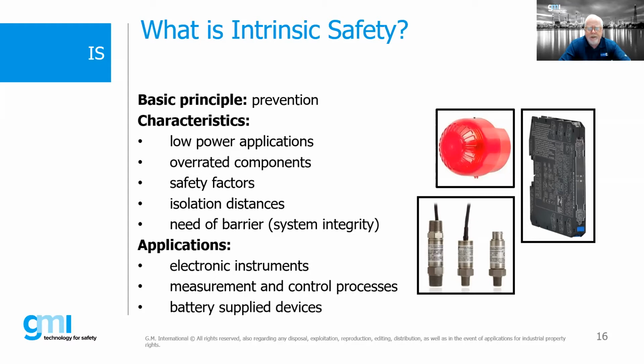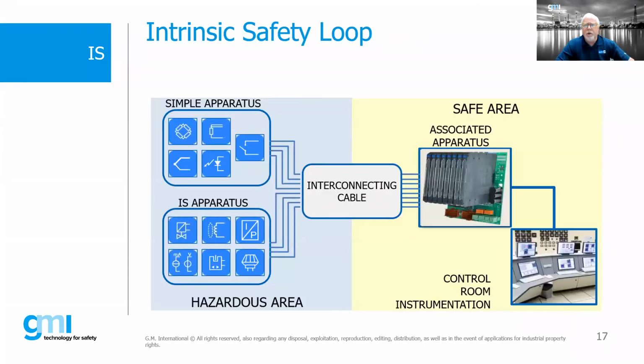Under IS applications, in many cases the cabling, the glanding, the installation requirements are not quite as rigid. So potentially you can save some money by adding a barrier and decreasing some of the things you'd actually have to do to make it a full flame-proof system. So there are some commercial advantages for using IS besides just the safety standpoint, plus the ability to work on the system.